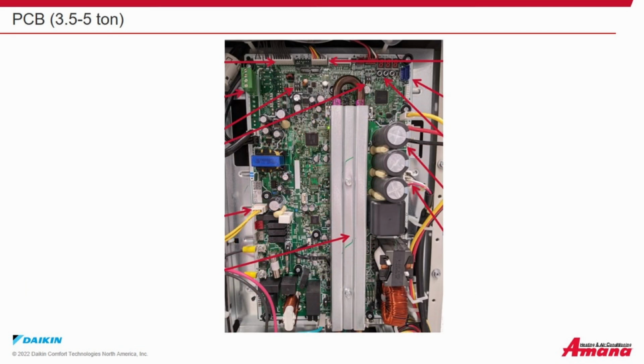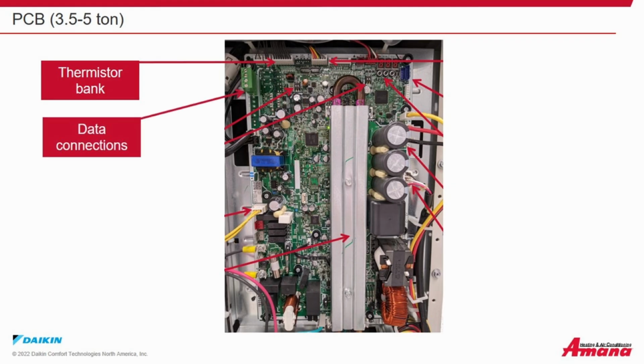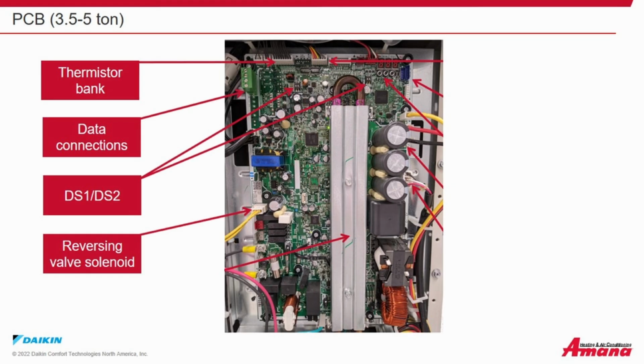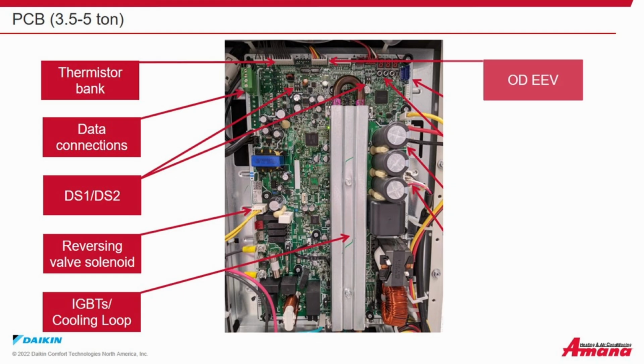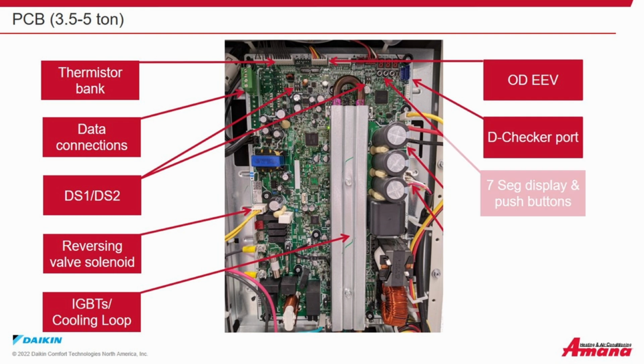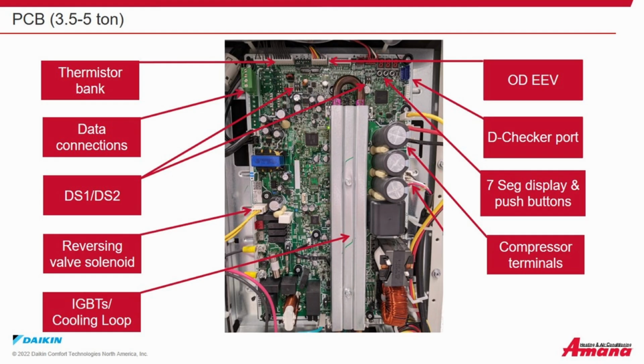On the circuit board of the 3.5 to 5 ton unit, we show the location of the thermistor bank, data connections, dip switch 1 and dip switch 2, reversing valve solenoid, IGBTs or insulated gate bipolar transistors, which are surrounded by a DX cooling loop, the outdoor electronic expansion valve, D-checker port, 7-segment display and push buttons, compressor terminals U, V and W, and the outdoor fan motor.